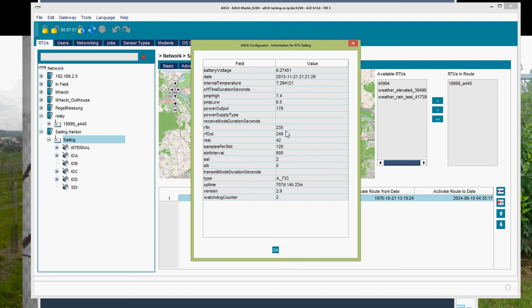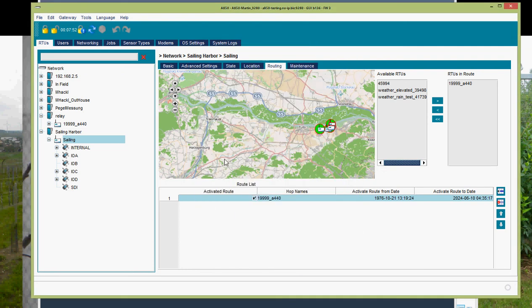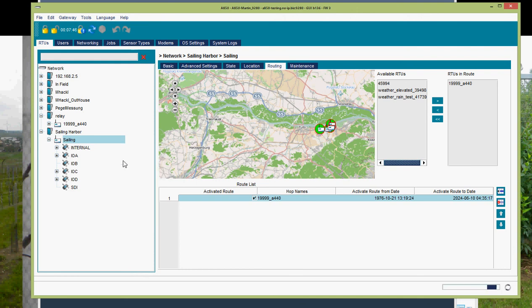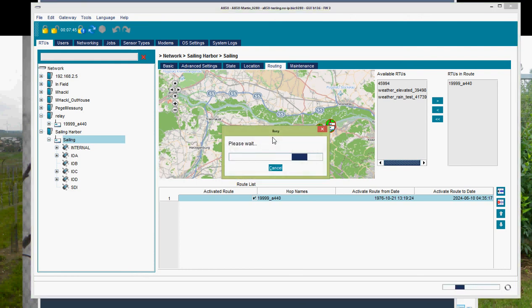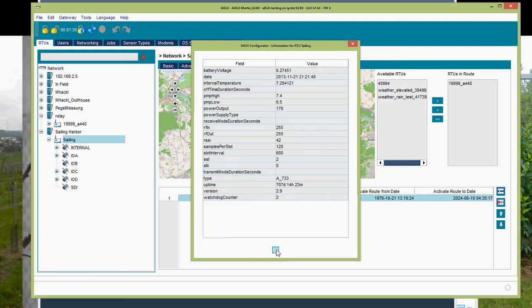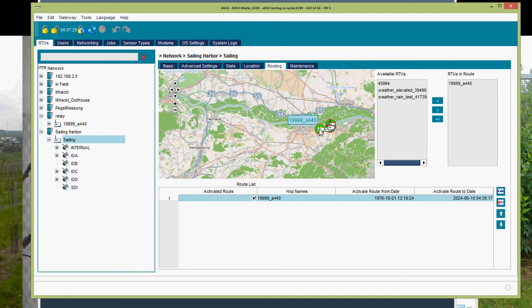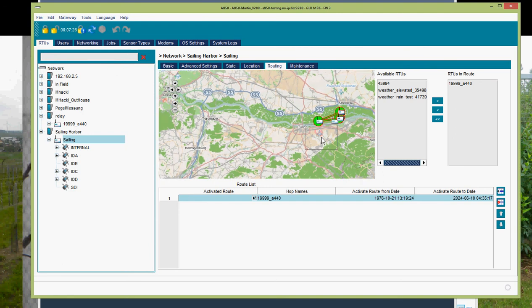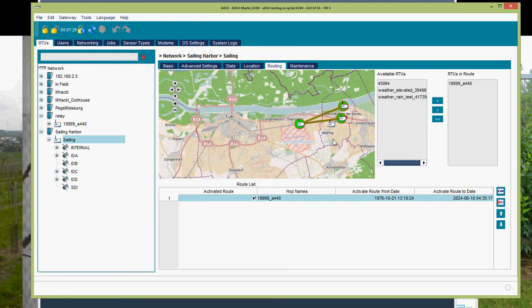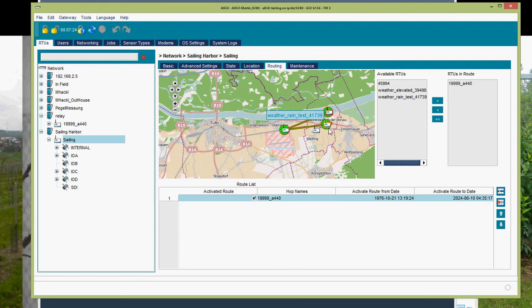It's still 235, 249, so the radio level is not better. Let's try again. Oh, it's much better. So I assume that the configuration was not updated correctly. So this helps to increase the radio level because the relay station on this position is higher than my A440 connection in this building here, so I'm jumping on a higher location to have a better contact to my RTU.